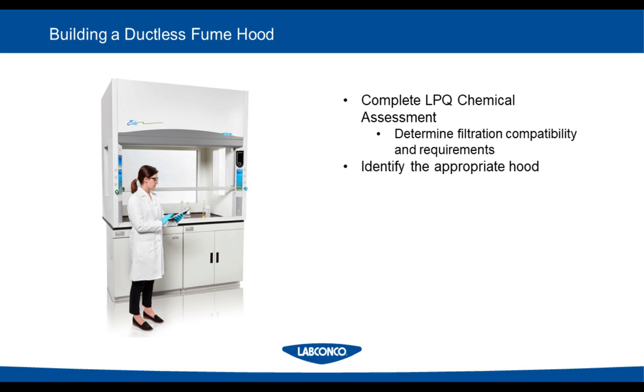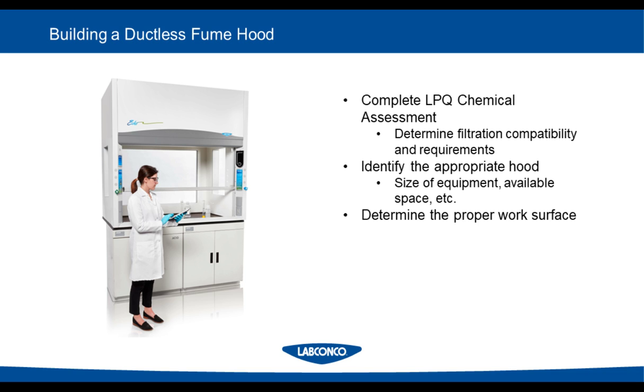And next, you need to identify the appropriate hood. As I mentioned in the previous slide, Labconco has a variety of sizes of fume hoods. So in identifying this, you'll need to take into account the size of equipment that you may be using, or the available space that you have in your facility, and ensure that you are selecting the proper fume hood for your application.